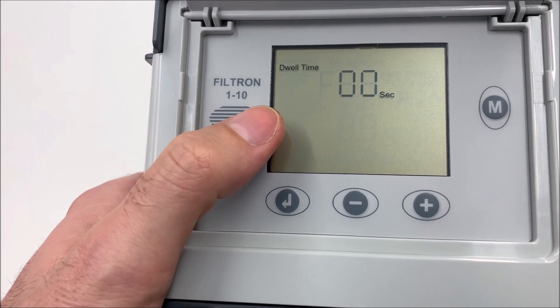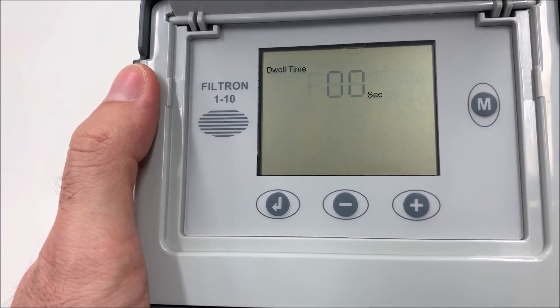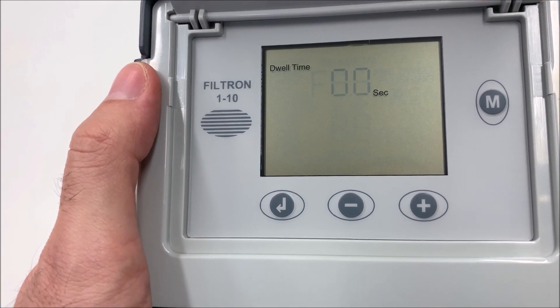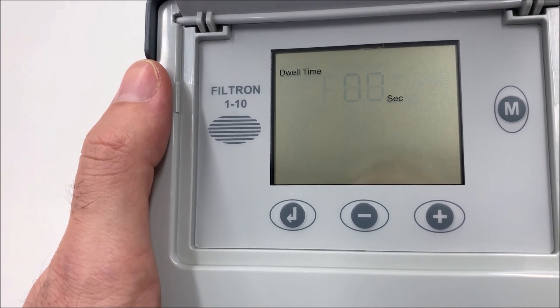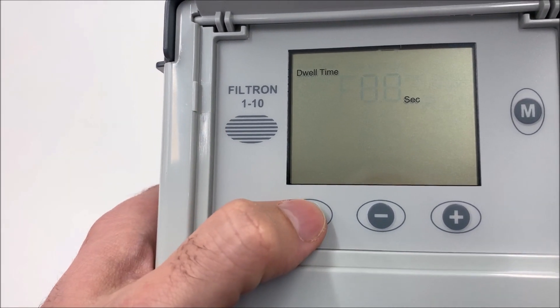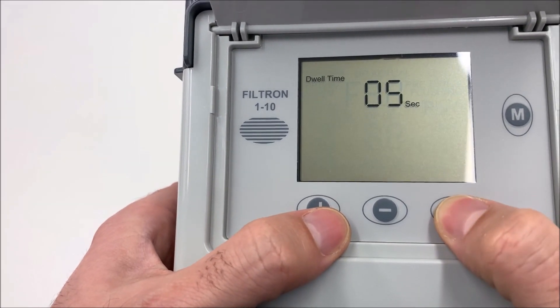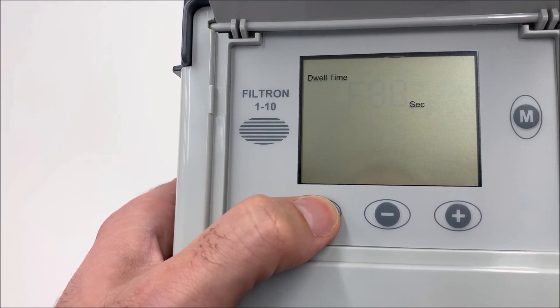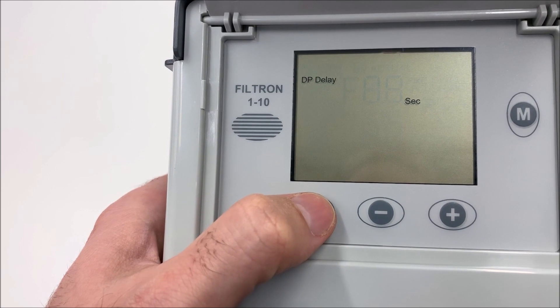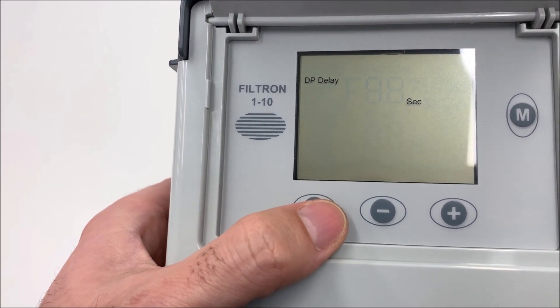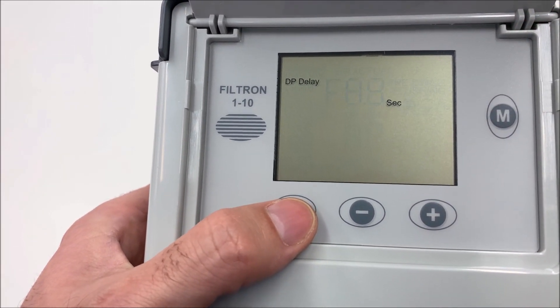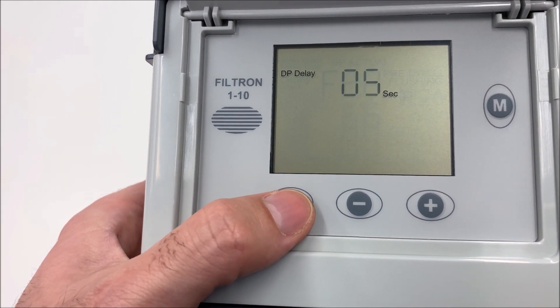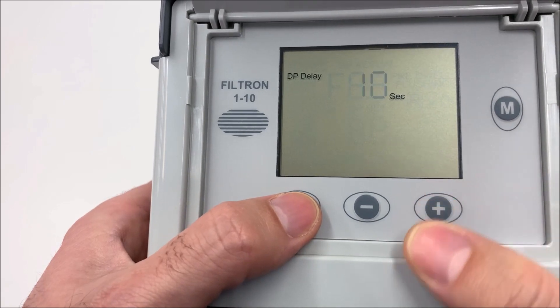Then we go for the dwell time. Dual time is the time between filters in case it is a multiple filter bank. You can preset eventually 10 seconds. DP delay is the time that the differential pressure should be over the preset value before we start the backwash. We will put 10 seconds.